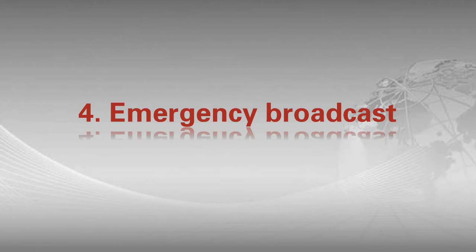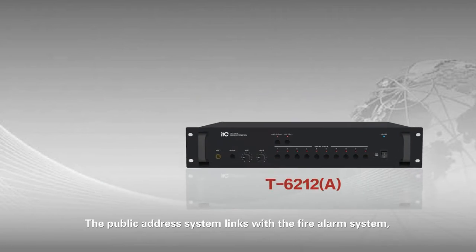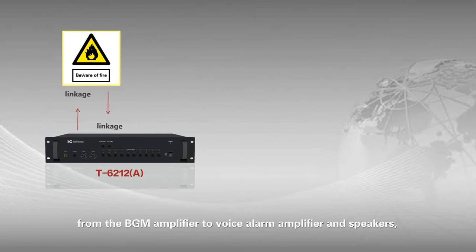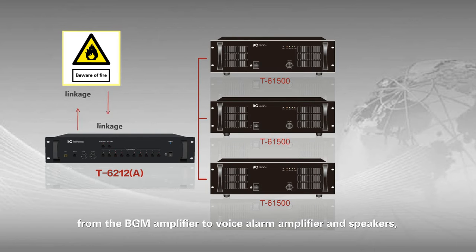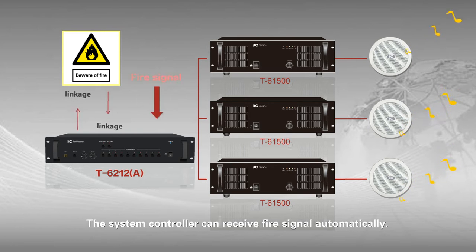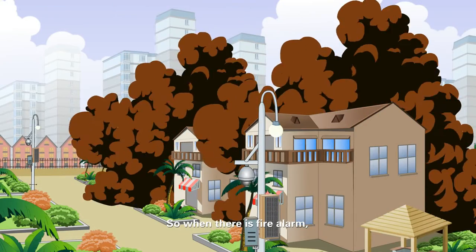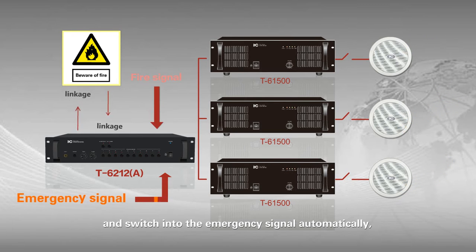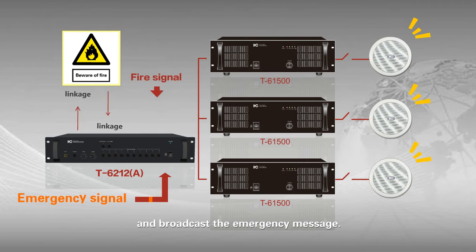4. Emergency broadcast. The public address system links with the fire alarm system, from the BGM amplifier to voice alarm amplifier and speakers, to save resources at maximum. The system controller can receive fire signal automatically. When there is a fire alarm, the public address system BGM signal is cut and switched into the emergency signal automatically, and broadcasts the emergency message.